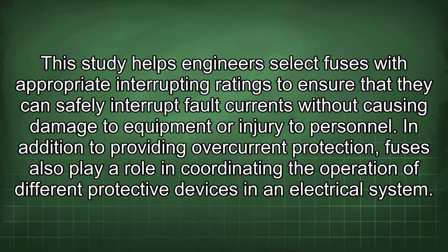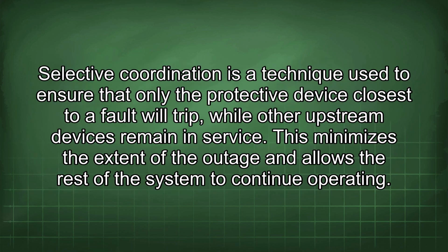In addition to providing overcurrent protection, fuses also play a role in coordinating the operation of different protective devices in an electrical system. Selective coordination is a technique used to ensure that only the protective device closest to a fault will trip, while other upstream devices remain in service. This minimizes the extent of the outage and allows the rest of the system to continue operating.